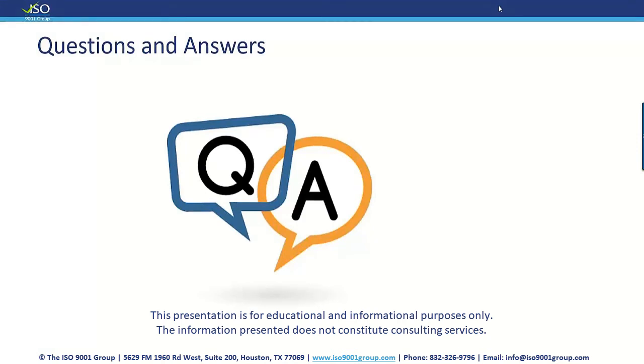Question number one, will my certification body write me up for having a verification program? You know what? They might write you up, but they should not, because just like they write you up on many other things in your companies, it's based upon what they're used to seeing and their experiences, and they may have the same opinion that everything should just randomly be sent out for calibration. But what we should do is point them back to the standard and say, Mr. Auditor, Mrs. Auditor, let's look at the standard here. It says that we can calibrate or verify or both. So your certification body should not be writing you up for verification.